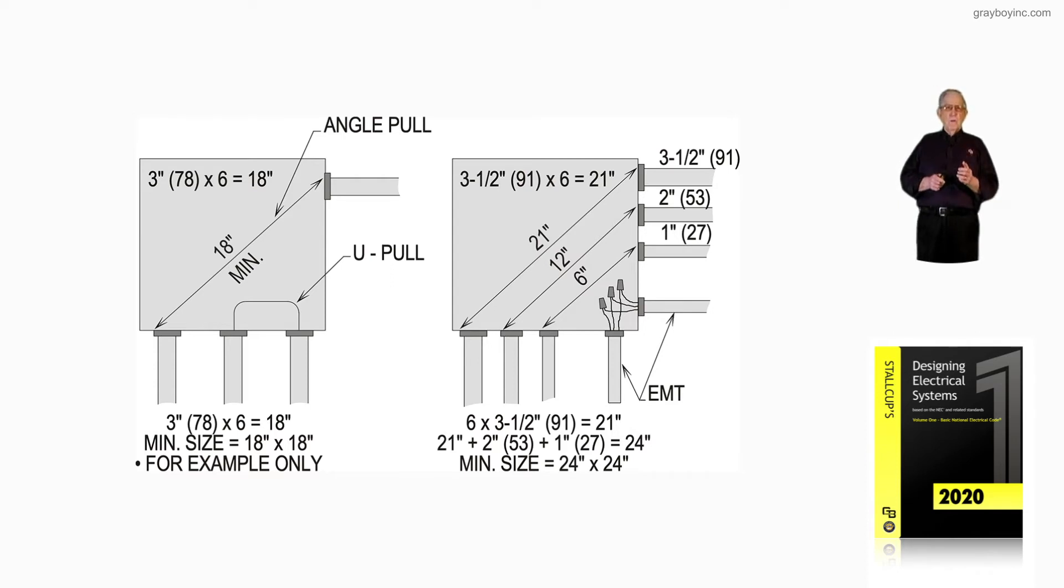So it's either angle pull or U-pull, and it's six times the largest conduit, plus the other conduits on a wall if they're present, such as the illustration to the right illustrates.